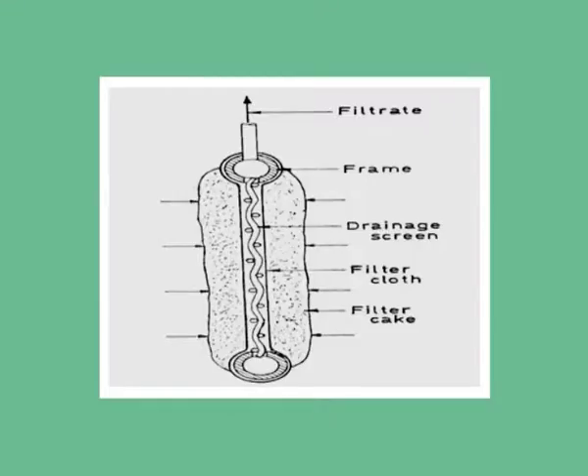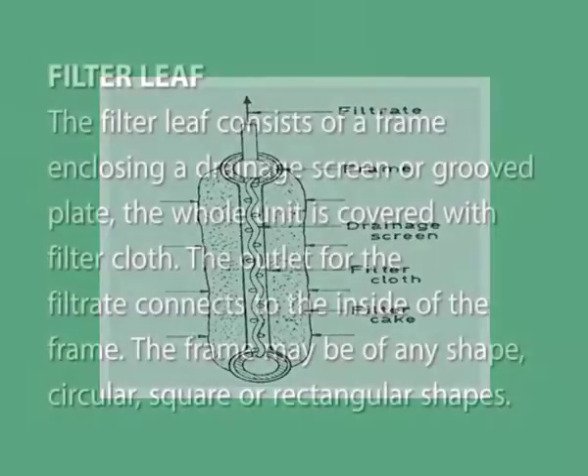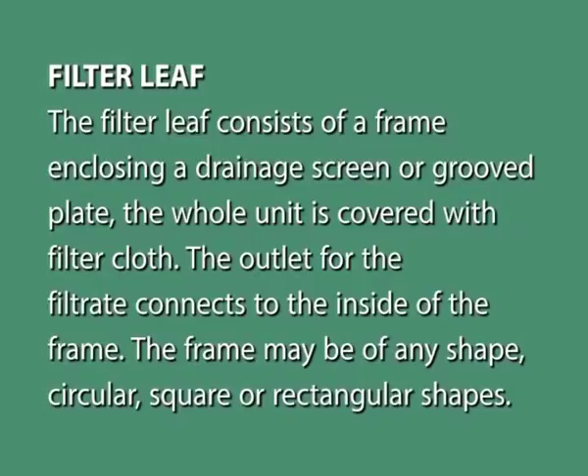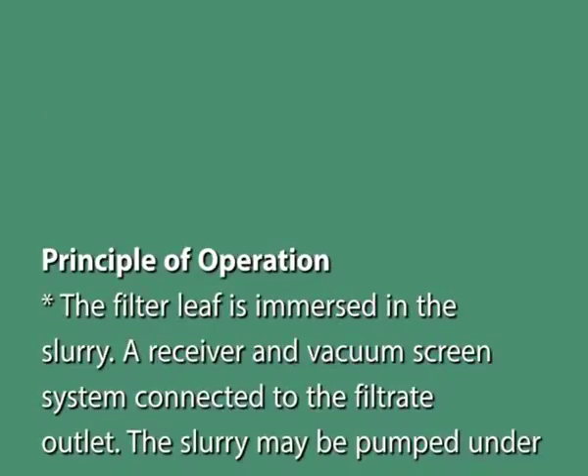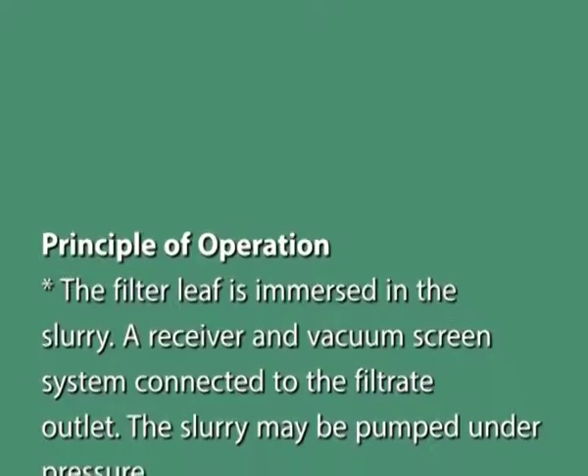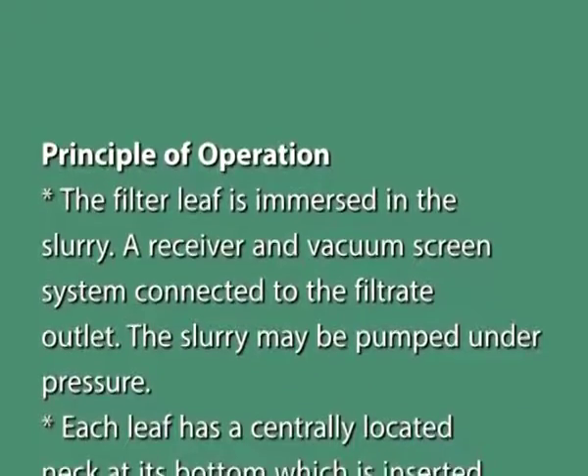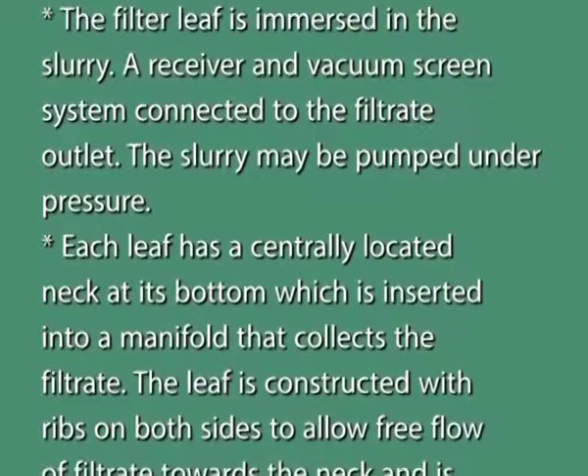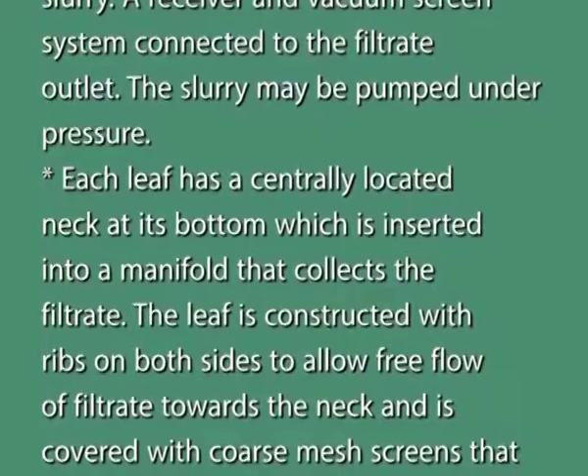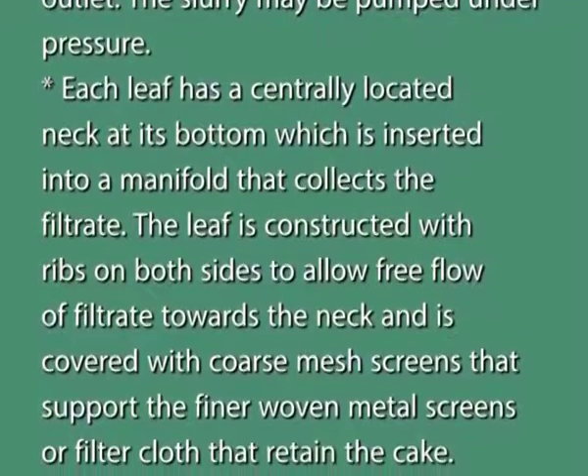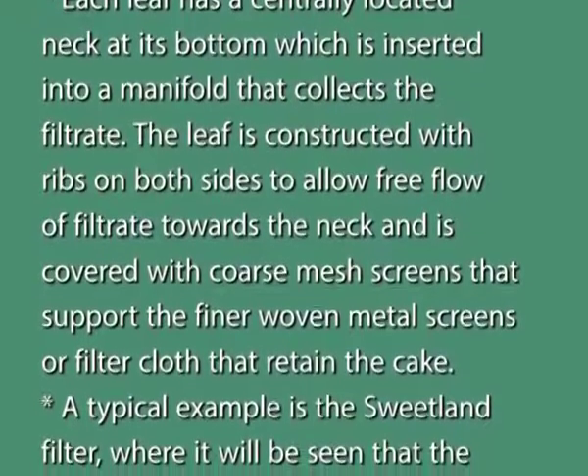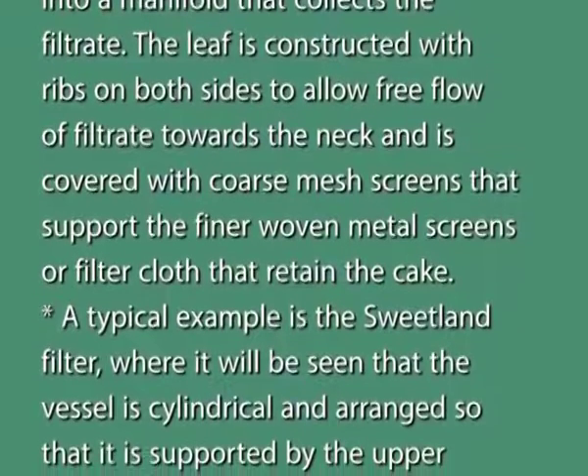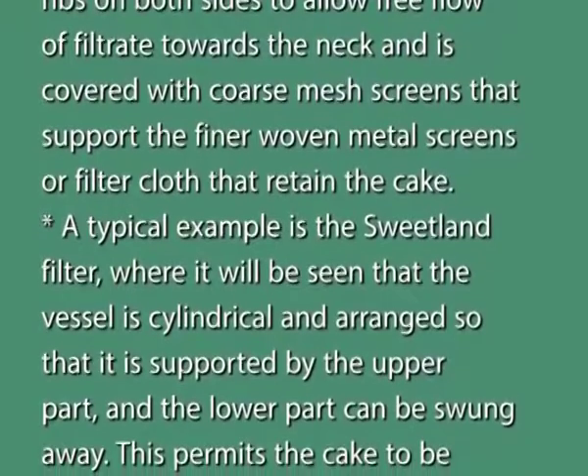The filter leaf consists of a frame enclosing a drainage screen or grooved plate, with the whole unit covered with filter cloth. The outlet for the filtrate connects to the inside of the frame, and the frame may be of any shape: circular, square or rectangular. In operation, the filter leaf is immersed in the slurry with a receiver and vacuum screen system connected to the filtrate outlet. Each leaf has a centrally located neck at its bottom inserted into a manifold that collects the filtrate. The leaf is constructed with ribs on both sides to allow free flow of filtrate towards the neck and is covered with coarse mesh screens that support the finer woven metal screens or filter cloth that retain the cake.